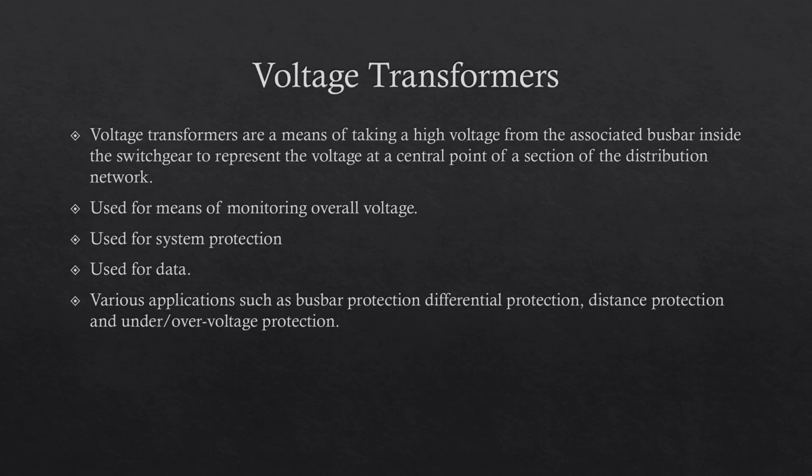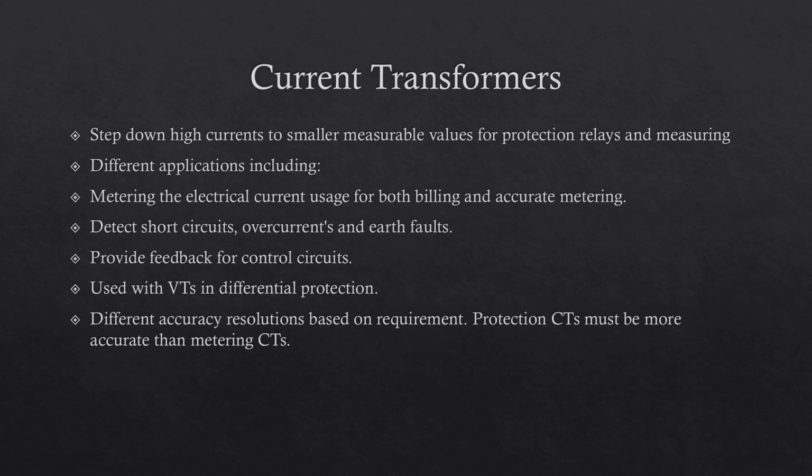So, what I just mentioned: current transformers. These current transformers, just like the voltage transformer, step down a measurement, but this time it's a high current to a more manageable current. So again, it could be by a factor of 100 or 500, or it all depends on what you have designed your protection scheme to, and also what equipment you are using and the relay, and the ratio in particular needs to be carefully considered.